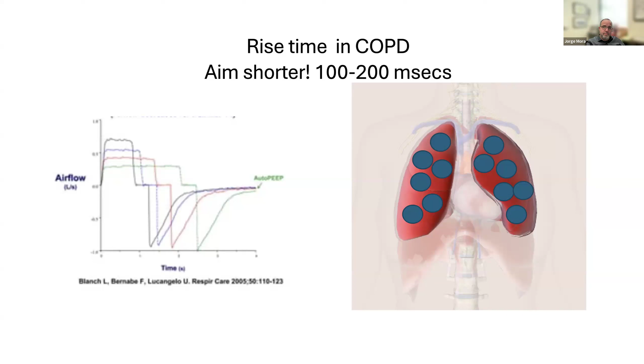Rise time is really important in certain diseases. Rise time is usually, depending on the device, defined by a number, or in many of the ventilators we use now it is defined in milliseconds. Philips used to have an equivalent measurement, where 1 is 100 and 2 is 200 milliseconds, etc. In patients with obstructive lung disease, you definitely want to aim for a shorter rise time. That's the time between the initiation of inspiration and the time you achieve maximum flow during that inspiration, or you're exerting your maximum level of IPAP. It needs to be short because at the end, what you're trying to do in patients with obstructive disease is minimize the time you use to exert the pressure you chose, to maximize the expiratory time, and hence avoid auto-PEEP and breath stacking.